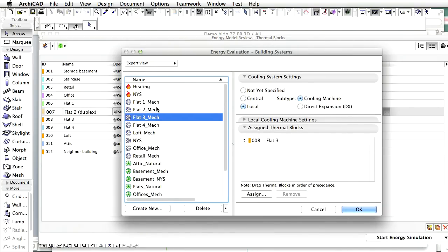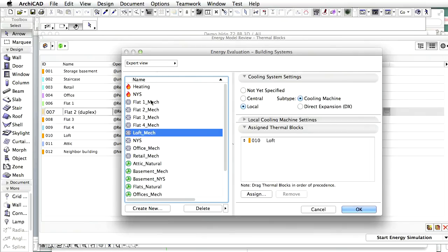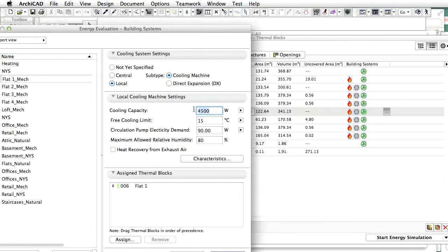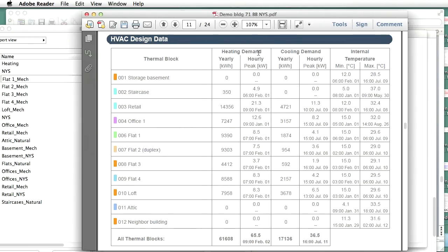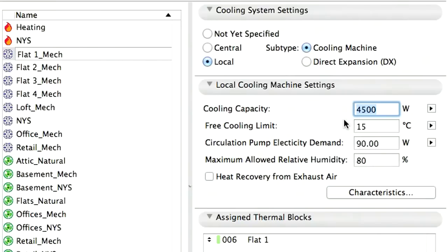The settings discussed below — other than the cooling system capacity and characteristics — are advanced settings, accessible only via the Building Systems Dialog's expert view. They are discussed in this demo movie to prove that even the expert level settings of EcoDesigner STAR are easy to understand for architects. The required cooling capacities are copied from the previously presented HVAC Design Data Table. The free cooling limit is an external air temperature limit: if the external air temperature drops below this limit, the external air is used directly to cool the building with no cooling mechanism applied. Circulation pump electricity demand is the peak energy demand of the pump circulating the refrigerant. The maximum allowed relative humidity is a set point used during the hourly energy simulation — if the indoor air's relative humidity increases beyond this threshold, the cooling machine turns off to avoid condensation.